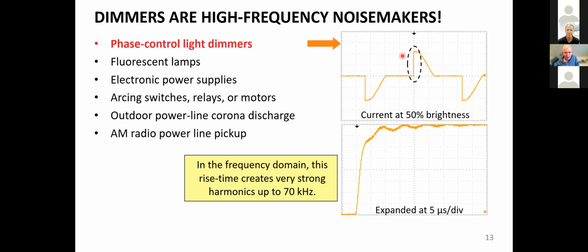If you expand this center area, you can see - I assume you know how dimmers work, but I'll explain briefly. A dimmer works by waiting to turn on the semiconductor device in it, either a triac or a silicon controlled rectifier, until the voltage reaches a certain point, and then it triggers this latching-on device, the triac, which remains conducting for the remainder of the cycle as long as current is flowing through it. Then it turns itself off and waits for another trigger in the negative direction.